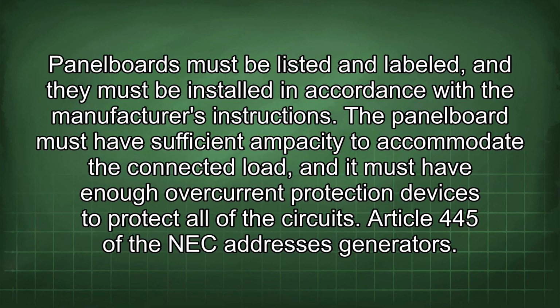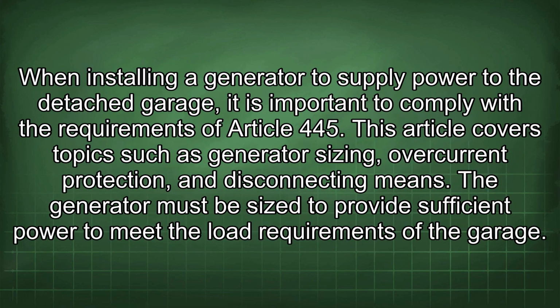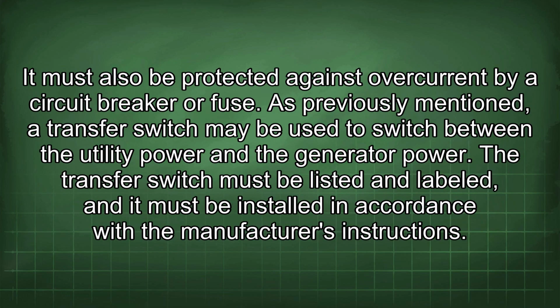Article 445 of the NEC addresses generators. When installing a generator to supply power to the detached garage, it is important to comply with the requirements of Article 445. This article covers topics such as generator sizing, overcurrent protection, and disconnecting means. The generator must be sized to provide sufficient power to meet the load requirements of the garage. It must also be protected against overcurrent by a circuit breaker or fuse.